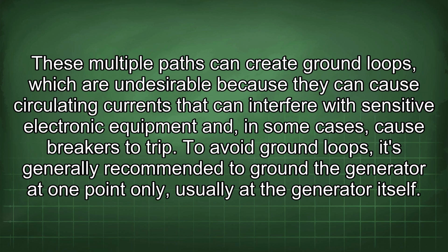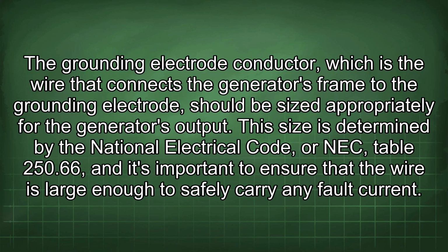To avoid ground loops, it's generally recommended to ground the generator at one point only, usually at the generator itself. The grounding electrode conductor, which is the wire that connects the generator's frame to the grounding electrode, should be sized appropriately for the generator's output. This size is determined by the National Electrical Code, or NEC Table 250.66, and it's important to ensure that the wire is large enough to safely carry any fault current.